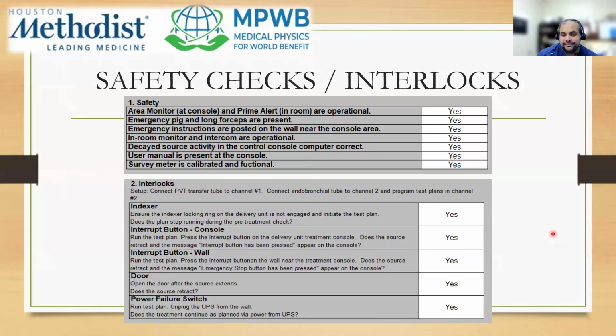because you can only mimic these scenarios and hope you don't have to use them during a treatment. The emergency button interlock is pretty much where you will be asked to go back and restart your treatment at the point from where you pressed the emergency button. So that's a little bit different than the other three interlocks.